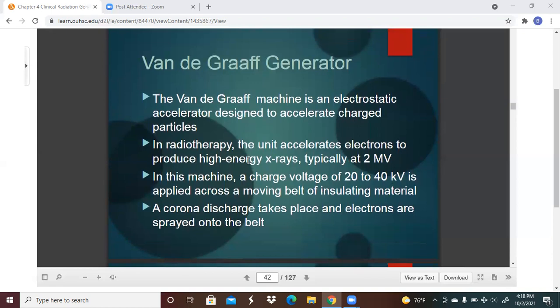So the Van de Graaff machine is an electrostatic accelerator designed to accelerate charged particles. So in radiotherapy, the unit accelerates electrons to produce high energy X-rays, typically at around 2 MV. In this machine, a charge voltage of 20 to 40 kV is applied across a moving belt of insulated material. A corona discharge takes place and electrons are sprayed onto the belt.